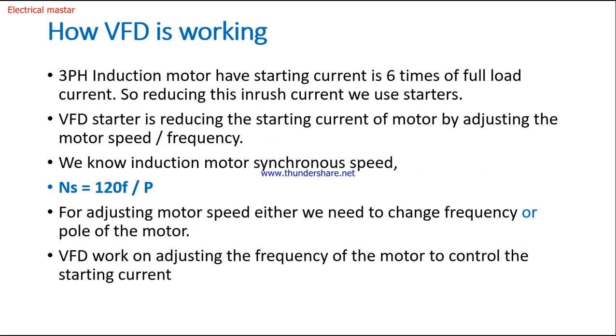Now we will see how VFD is working. The starting current of a three-phase induction motor is six times the full load current. To reduce this starting current we need a starter. There are different types of starters: DOL, star delta, auto transformer, soft starter, and VFD. What makes VFD different is that it can control the starting current and also control the motor speed throughout the entire operation.